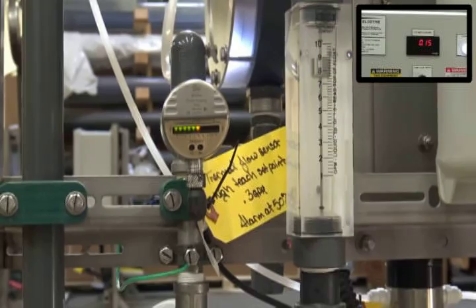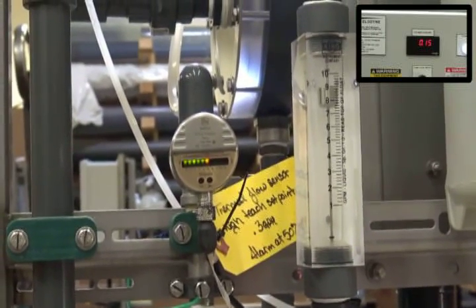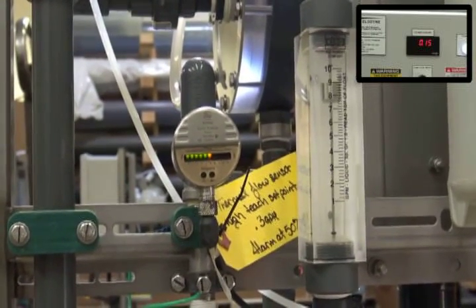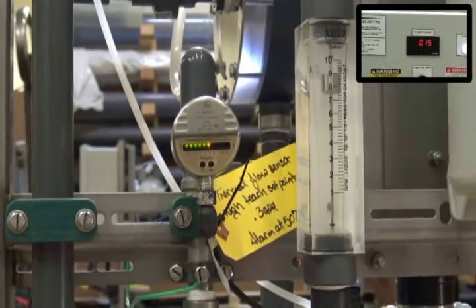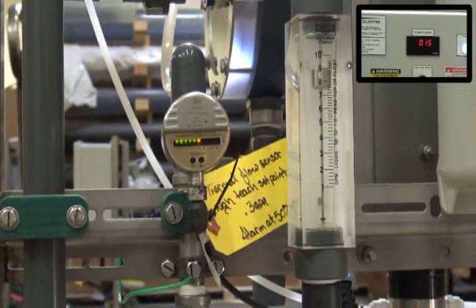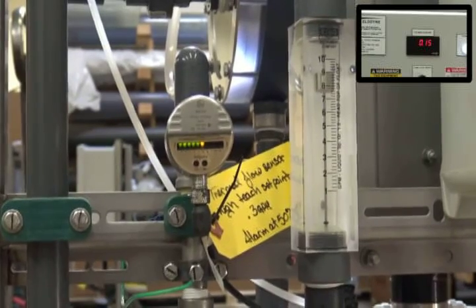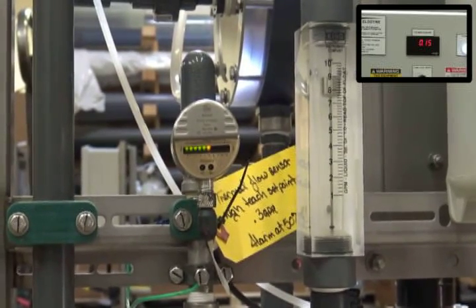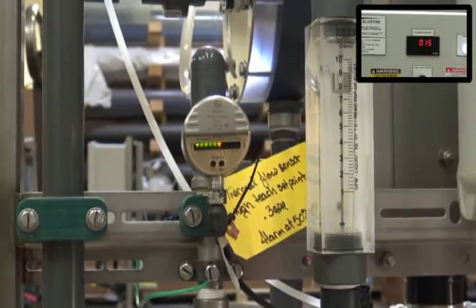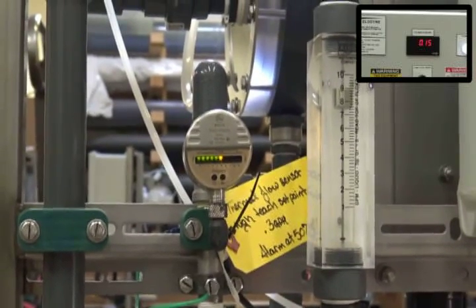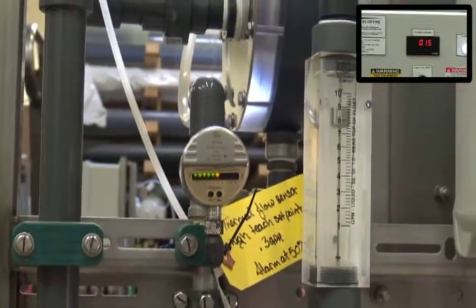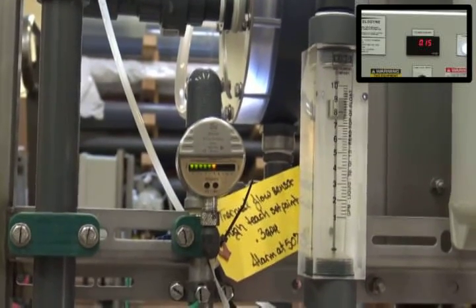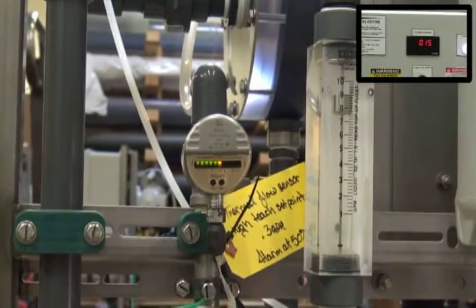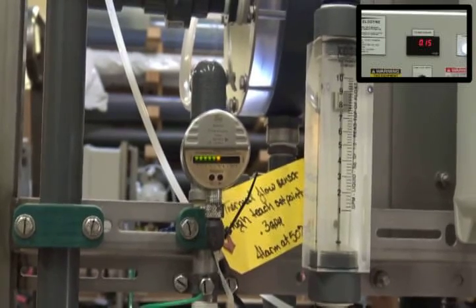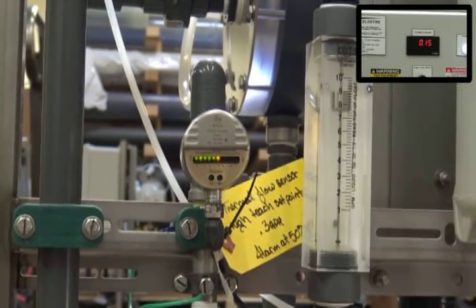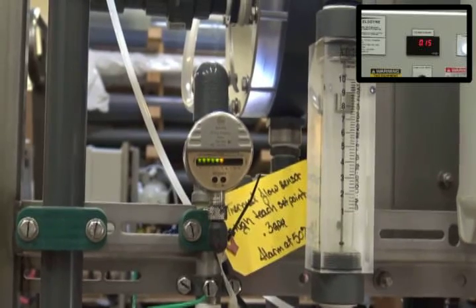So now that's a good opportunity though, because with that being said, we can actually fine tune this switch point by moving that red light back and forth left or right. If you're getting nuisance alarms, move it to the lower side or the left side. If you're getting not enough alarm, or when you think you should alarm, it's not alarming, but it's getting real close to that light, you can move that light to the opposite direction, towards the right, and it will alarm out quicker. It's kind of like treating it like a time delay on the switch point.